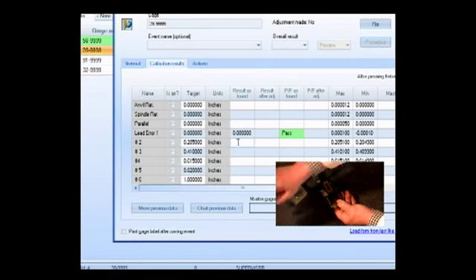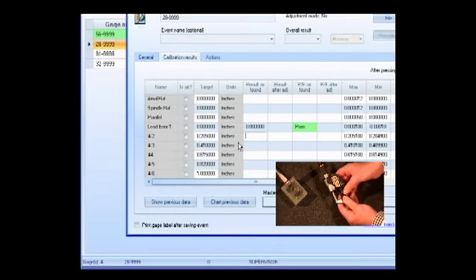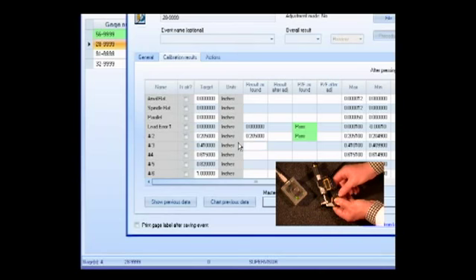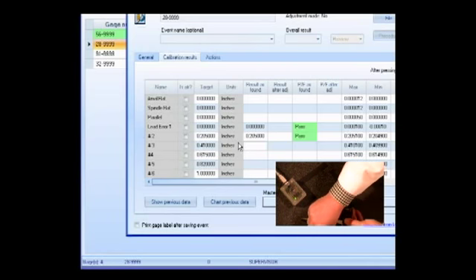the next checkpoint. Right. So basically, this is saving you from setting down your micrometer, entering the data in manually, then coming back and picking your micrometer up again. You can just sit there and keep the micrometer in your hand, keep taking measurements, and just keep collecting data as you go. I'll show you how simple it is. I do my next test point, push the button, automatically inputs it in. It was linear. That measured 205 on the money, exactly as you'd want. Shows pass and cycles to the next event.